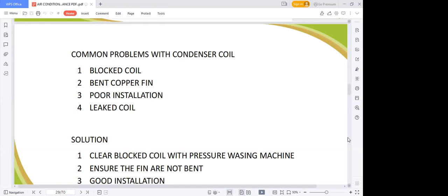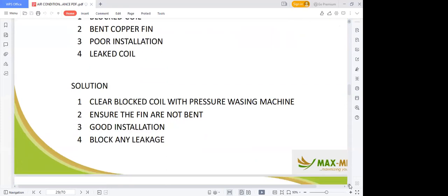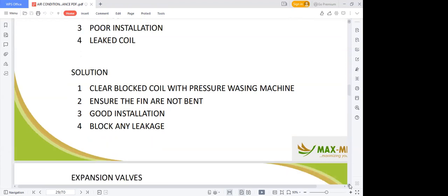And how do you find the leak? They have gas leak detection equipment that you can use. Then the cheapest form of detection of leakage is to use soap water. The same thing is applied for those pumping tires. Once your tire is leaked, your mechanic will buy soap, put it inside water, and start pouring it around any possible place that is leaking. It brings it all out. So those are the solutions there. Clear blockages, ensure the fins are not bent, do good installation, then block any leakage.